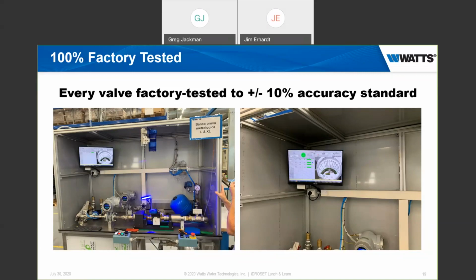And what we are doing is testing that valve at 4 points within its range. We're taking a reading at its lowest point, and at its highest point, in other words, its highest flow rate, and then 2 points in between. The standard it must meet on all 4 points is that it must be within plus or minus 10% of the actual flow rate. Every single valve is tested. Every single valve leaves the factory certified that it's going to be plus or minus 10% of the actual reading on the needle. So you'll see the test setup there on the left.